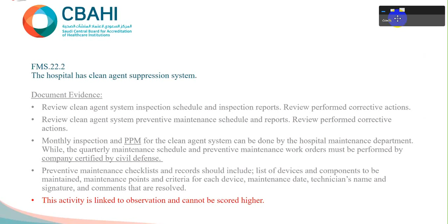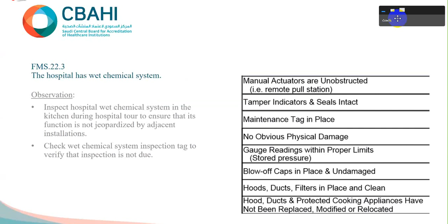The hospital has wet chemical. Wet chemical, usually we have it in kitchens. This is a sort of equipment. As you see here, we have the hoods or the nozzles, along with the triggers. In the cylinder here, there is water and some chemicals, and in the stainless steel box there are many cylinders. Contents include calcium carbonate, etc. And we have a trigger adjusted so that with temperature this could be operated.